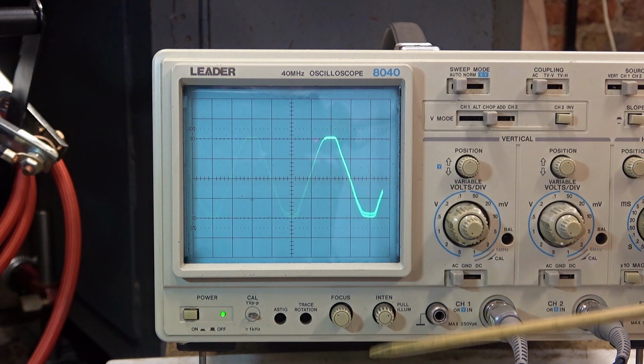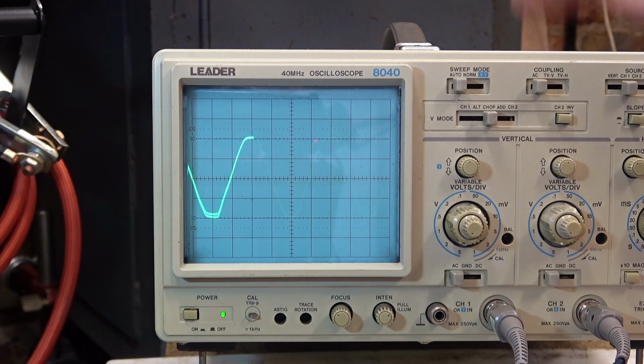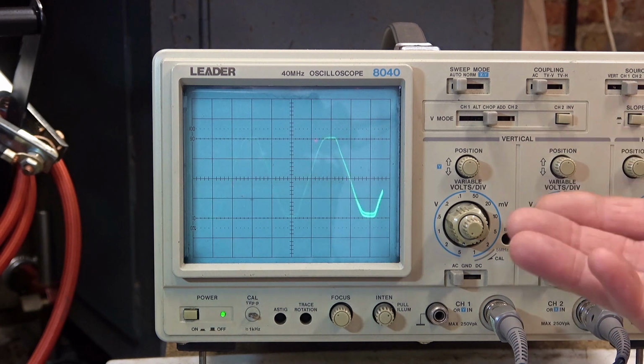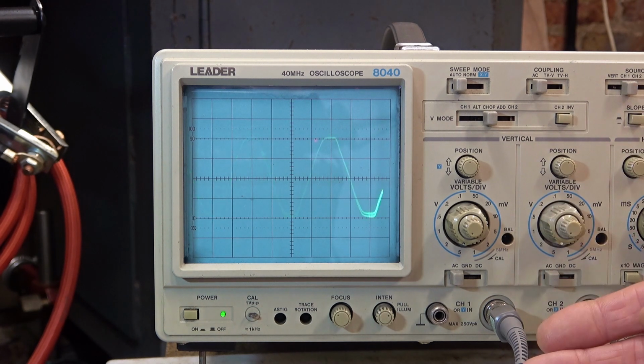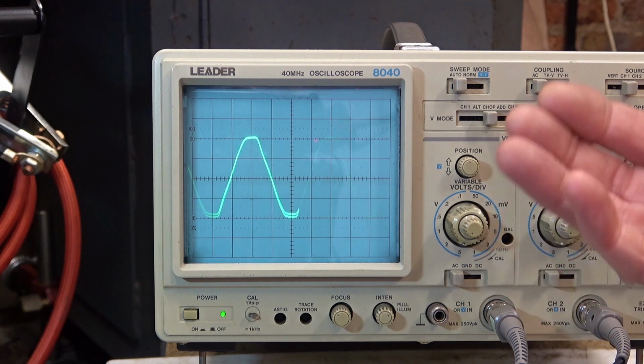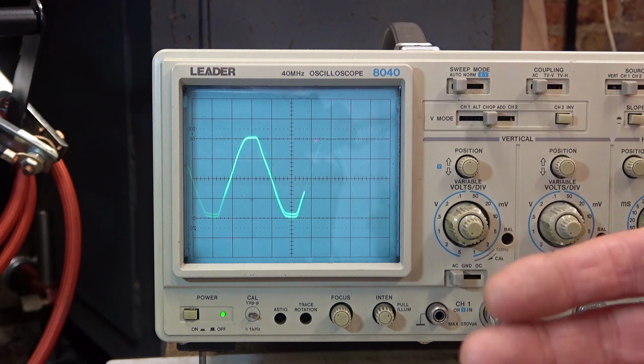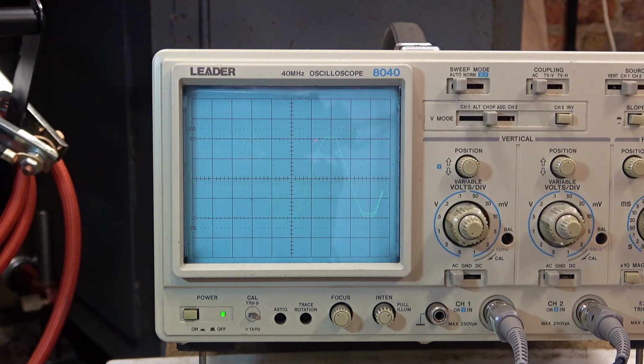Now, to put my scope probe across both L1 and L3, I would need an isolating transformer or a differential probe. And I looked online, cheapest I could find was £60, and then it goes anything up to £1,000. Well, I'm not paying that.